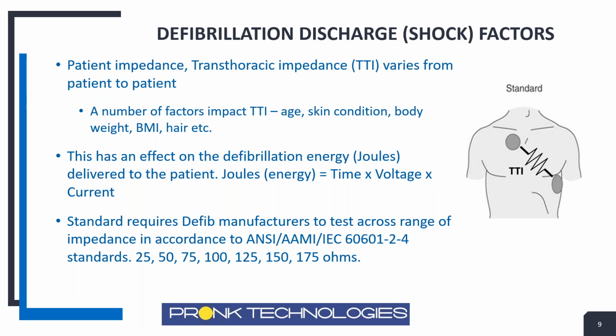So it's important to understand this as a reference, because if you're investigating incidents, and the nurse is saying they had to really energize the patient at a high energy, well, maybe something's not functioning properly across a wide range of impedances. It may be good to test across those impedances.